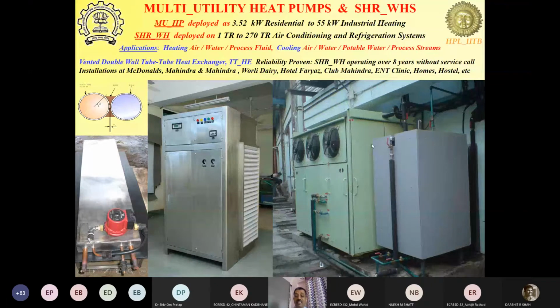Also, the excess heat after recovering hot water was dispensed using evaporative condensation. In evaporative condensation, on one side you have water evaporating, and on the other side you have the refrigerant condensing. We will see shortly what type of patented equipment we deployed there. That was a rotating contacting device, an adiabatic contacting device. Using this device, we were able to reduce the condensing temperature significantly, and that led to reduced condenser pressure, reduced pressure ratio across the compressor, and so reduced power consumption of the compressor.